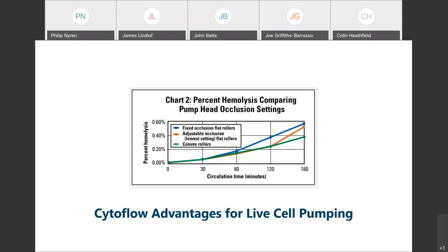So the Cytoflow heads, functionally, rely on the interaction between a unique convex roller and a concave occlusion bed, which further minimizes the impact forces on the fluid as the pump operates. They also incorporate large diameter rotors that enable you to deliver high flow rates at lower speeds. And lower speeds, or running the pump at the lowest possible speed to deliver your flow rate, will also optimize cell survivability, and maintain the integrity of the fluid that you happen to be pumping. So that's what I have on Cytoflow.